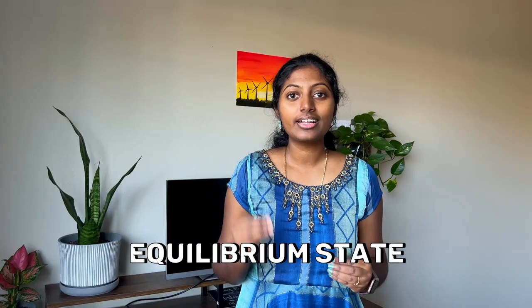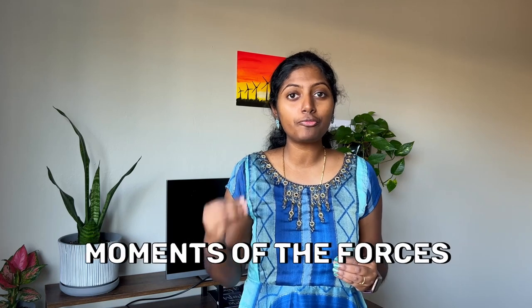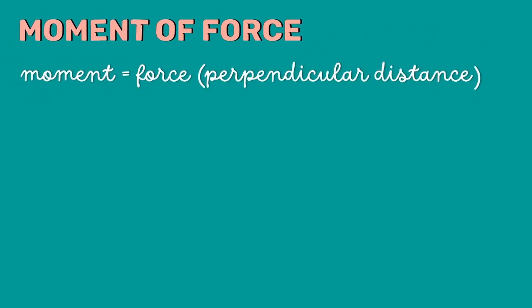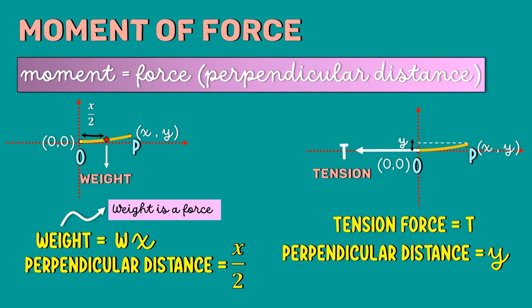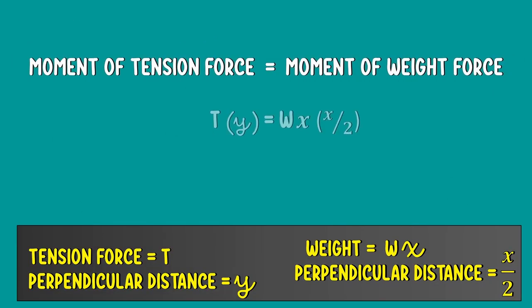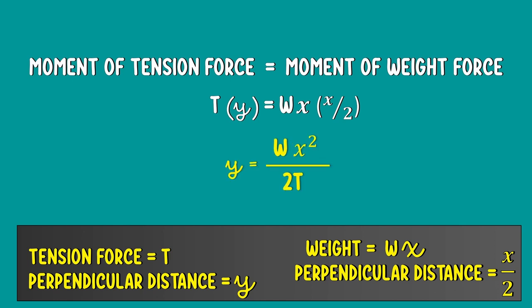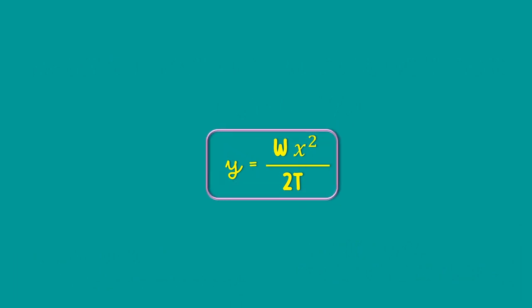Here, the conductor is in an equilibrium state. Therefore, the moments of the force about the point O will be equal. We know that the moment is force multiplied by perpendicular distance. Equating the moments, we get TY equals WX multiplied by X by 2. This means Y equals WX squared divided by 2T.